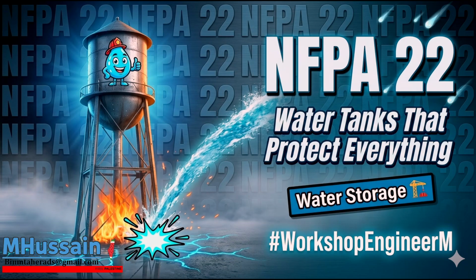Right. And that electrical capacitor analogy holds up really well under fluid mechanics. A fire pump is a highly tuned piece of rotating equipment. It's engineered to perform on a very specific pump curve. So if the input is jumping all over the place, the output will too. If the suction pressure feeding that pump is constantly spiking and dropping, the pump's discharge pressure will oscillate violently, which causes hydraulic transients. Water hammer. And that shock wave travels throughout the entire downstream sprinkler system, potentially blowing out fittings or sprinkler heads before the fire even reaches them. So the break tank guarantees a consistent, predictable suction pressure. It decouples the pump's performance from the chaos of the municipal grid.